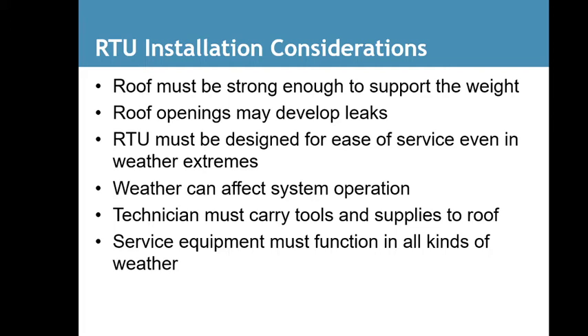Roof openings may develop leaks, so this is something that should be done by a professional roofer. You need someone to take the curb, which is the box that sits underneath the unit. Again, it's 4 to 6 inches tall, and it's ductwork. It fits the ductwork of the unit that you're setting on top of it, and it's got to be sealed on the roof. This has got to be able to be worked on in all kinds of weather.